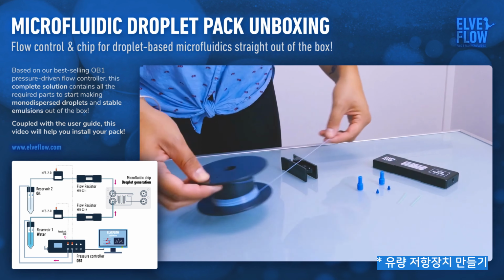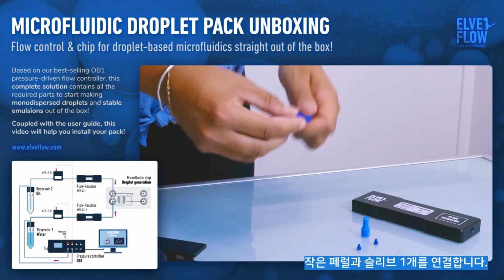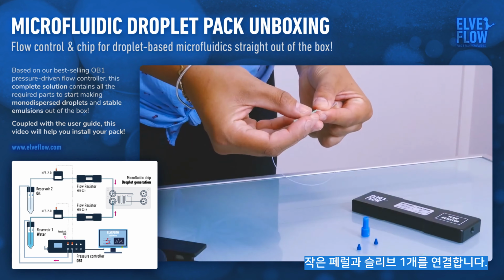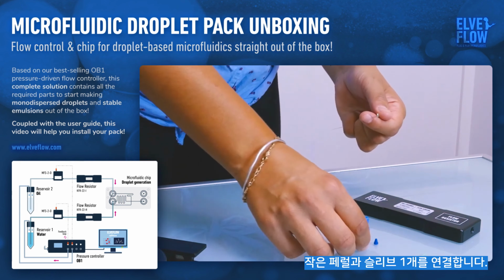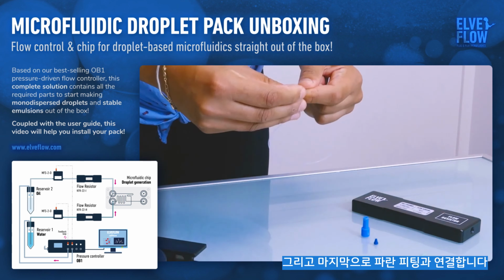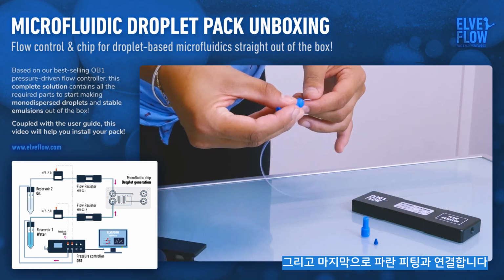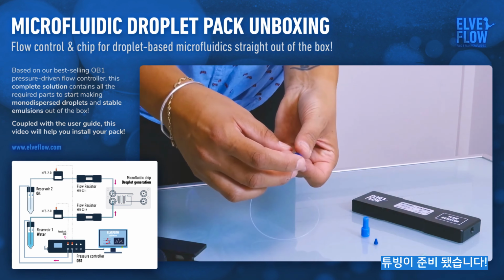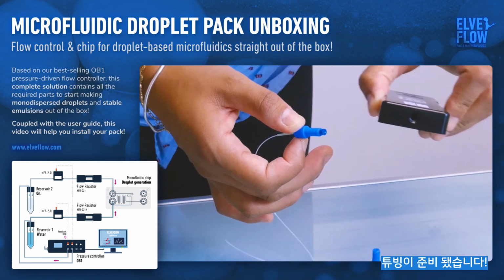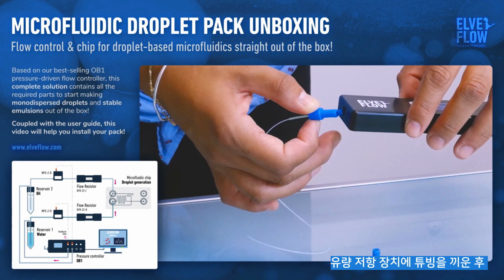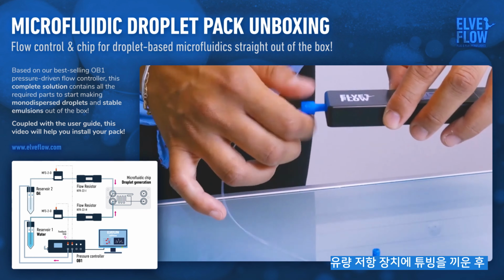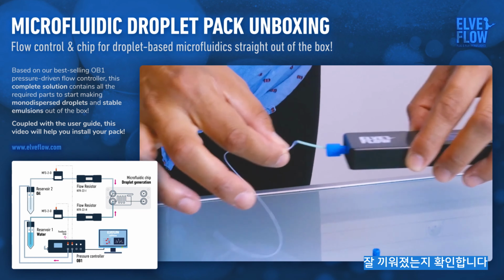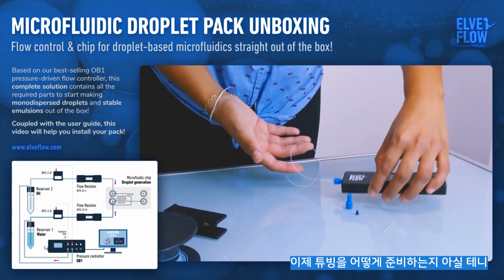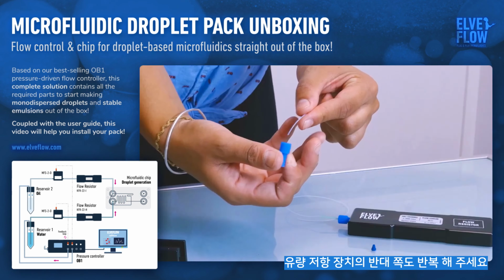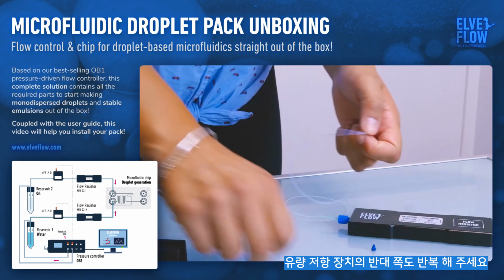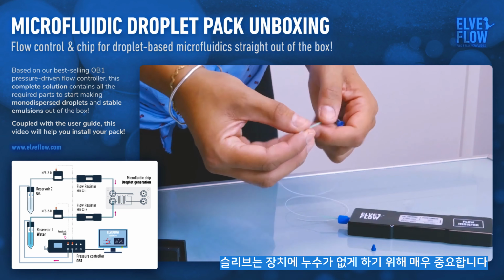For the flow resistor, cut a piece of tubing, slide on a blue fitting, then a sleeve, and finally a small ferrule, narrow end first. Your tubing is ready. Screw it into the flow resistor and make sure it's well attached. Now that you know how to set up the tubing, repeat for the other side of the flow resistor. And don't forget the sleeve. It's very important for a leak-free setup.